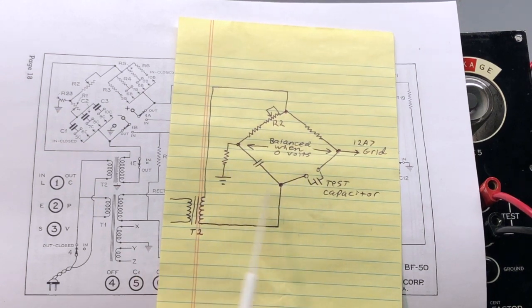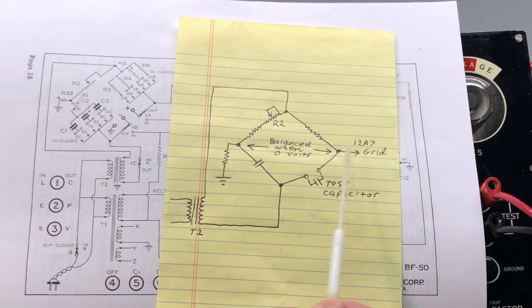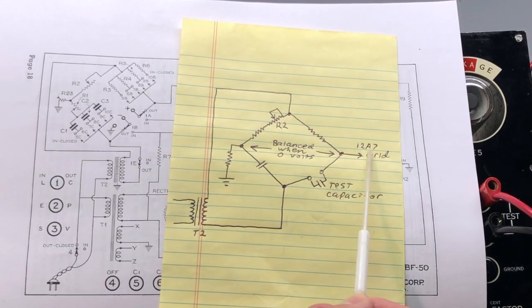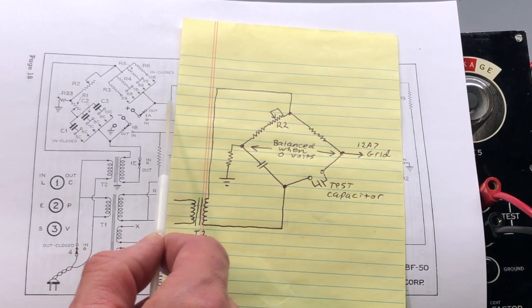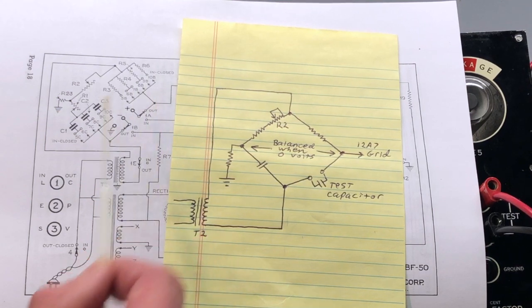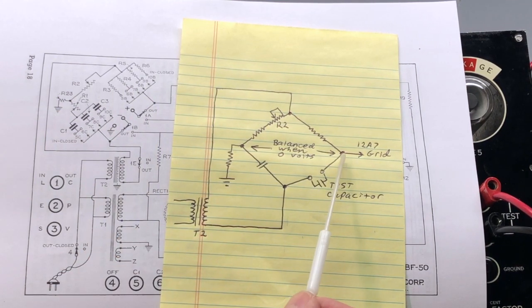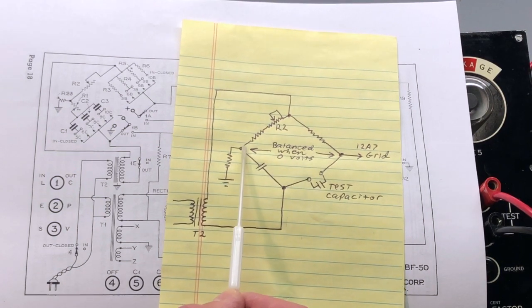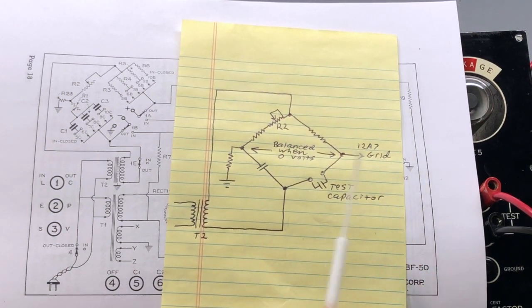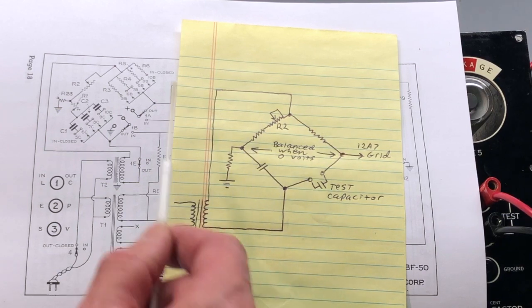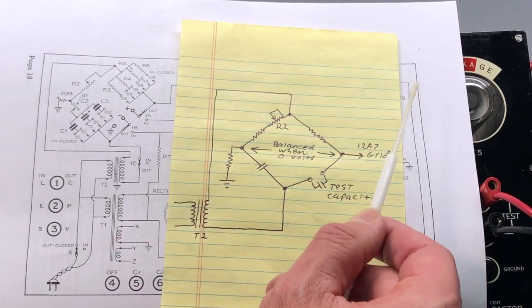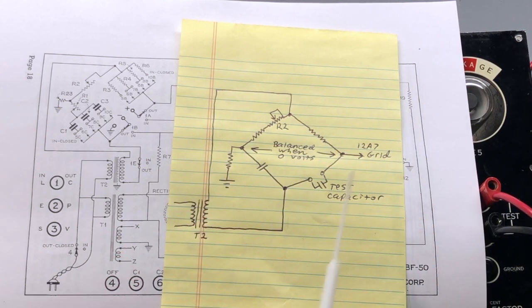So here's the basic bridge circuit. We have a reference to ground on this side, and this side goes to the grid of the 12A7 tube, which is this connection right here. Now, the bridge is said to be balanced when you have a 0 voltage condition between this point and this point. And ultimately, that's what the eye tube will be looking for through that amplifier circuit, and then which ultimately drives the eye tube.